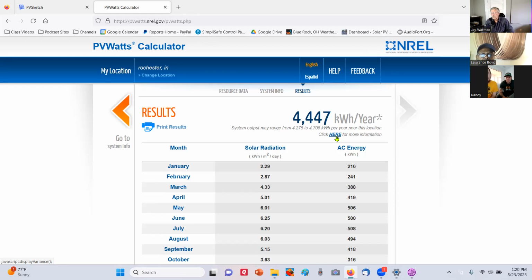Now you say that the machines draw how much? Let's do 1,200 watts times 2. If I ran those 24 hours a day, that's 2,400 watts times 24 hours, which is 57,600 watt hours. So 57.6 kilowatt hours per day times 30.5 gives me 1,756.